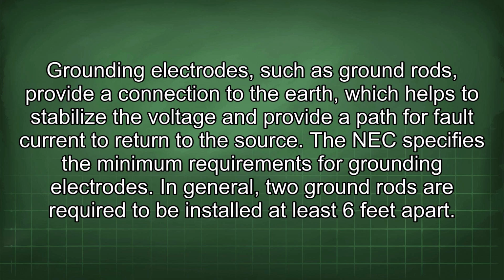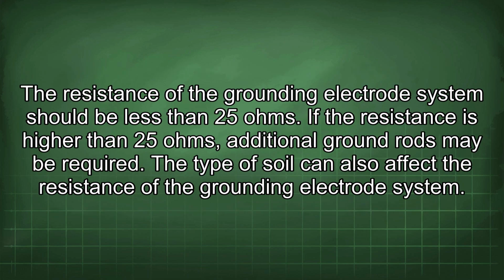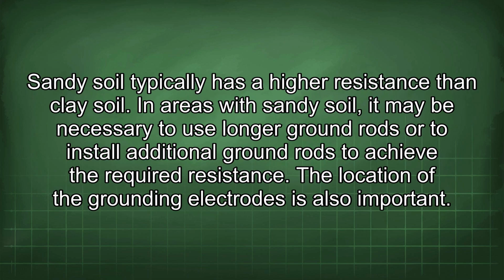The NEC specifies the minimum requirements for grounding electrodes. In general, 2 ground rods are required to be installed at least 6 feet apart. The resistance of the grounding electrode system should be less than 25 ohms. If the resistance is higher than 25 ohms, additional ground rods may be required. The type of soil can also affect the resistance of the grounding electrode system. Sandy soil typically has a higher resistance than clay soil. In areas with sandy soil, it may be necessary to use longer ground rods or to install additional ground rods to achieve the required resistance.